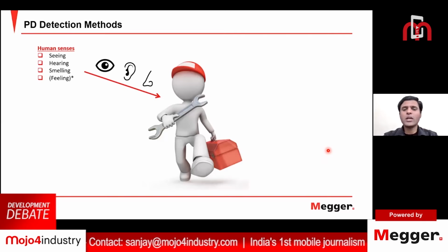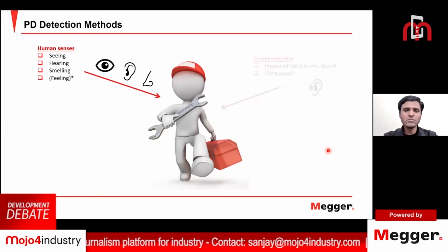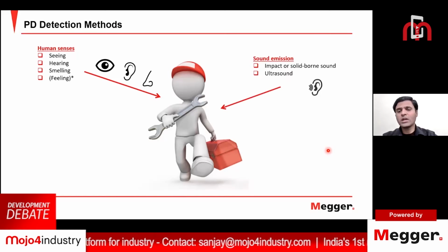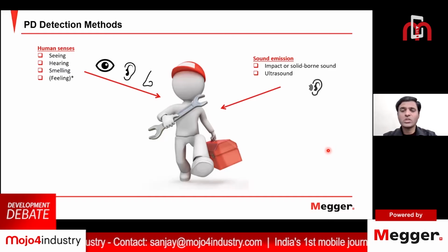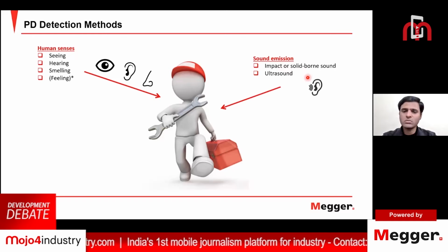If the PDs are emitting light, the human eye can identify it. If there is a chattering sound in the audible range, the human ear can sense it. If there is a smell because of burnout, the human nose can feel it. However, if the PDs are emitting signals in the acoustic range which are out of the human audible range, that means 20 to 100 kilohertz, different sensors can be used, acoustic sensors, to sense that particular frequency range and identify the effect and the intensity of the PDs in the particular asset. Ultrasound also has different sensors available.